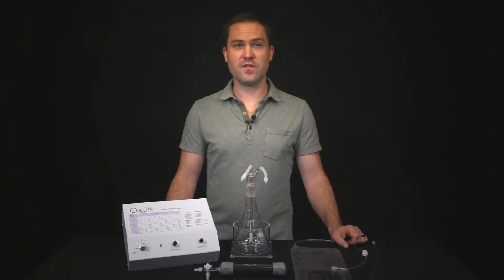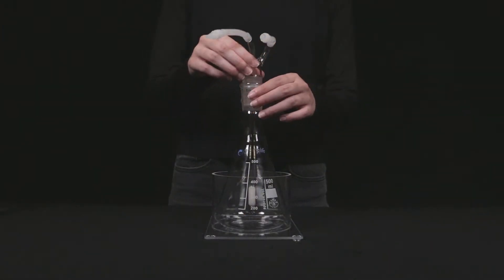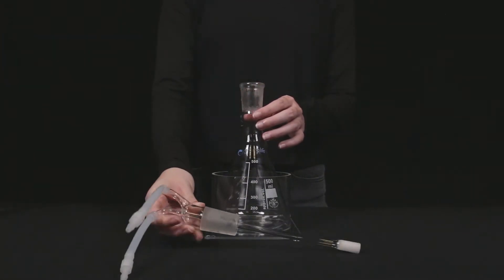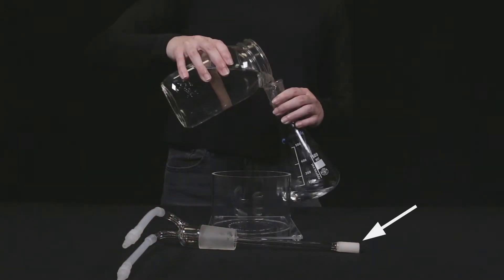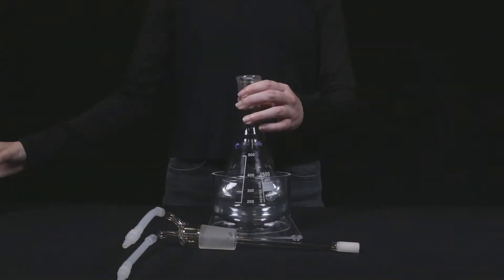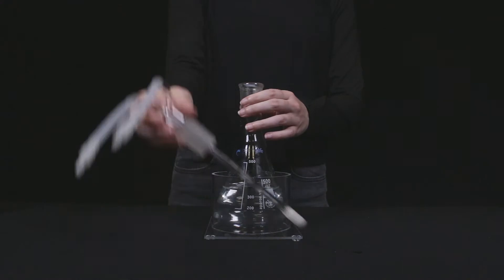Before connecting the humidifier, first you will want to fill it to the correct water level with either distilled or purified water. For the case of the 500ml bubbler humidifier combo, you will want to take the stem out, fill the jar until the diffuser is covered, put the stem back in the jar, and place the jar in its stand.